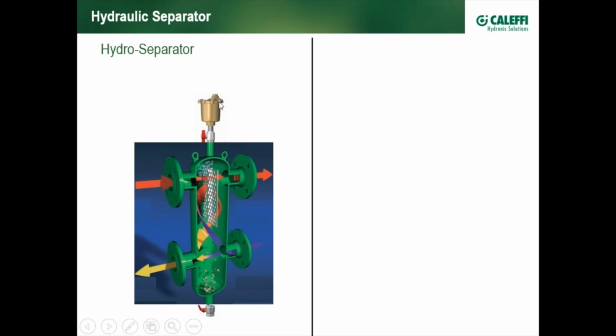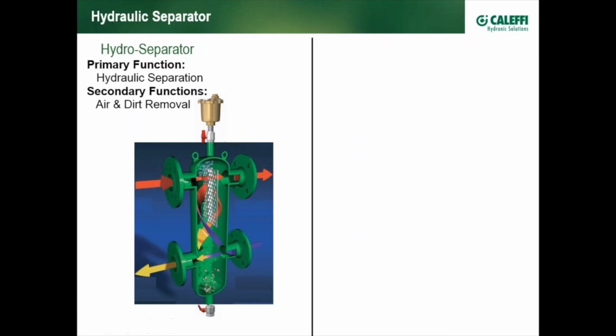Thus, all of our hydraulic separators come with a standard high-capacity air vent up here. And debris catches in the bottom, although it's not facilitated with any type of mesh. So the principal function of a hydraulic separator from Caleffi is hydraulic separation, or primary secondary. And secondary functions are air and dirt removal. Been used for a long time.